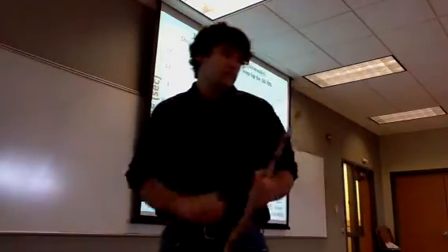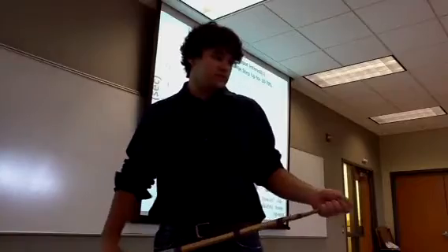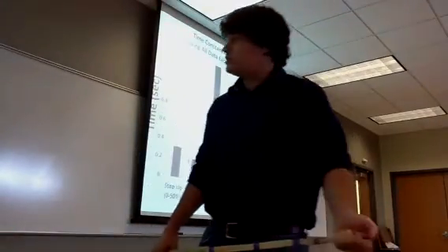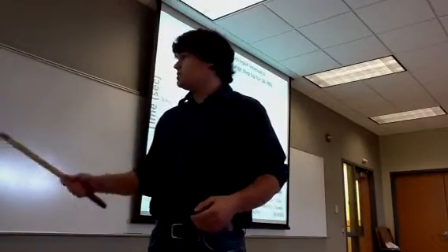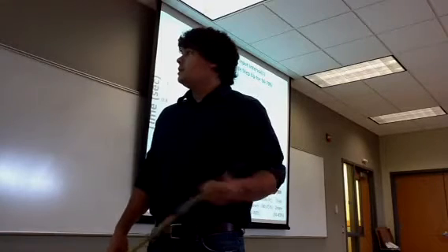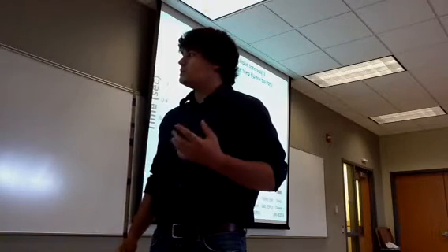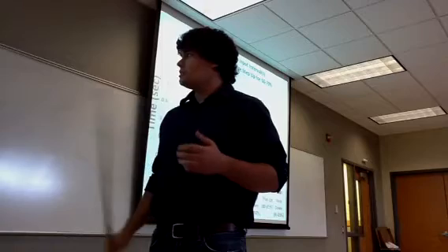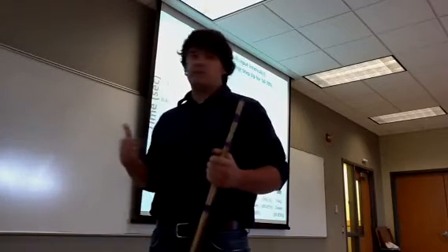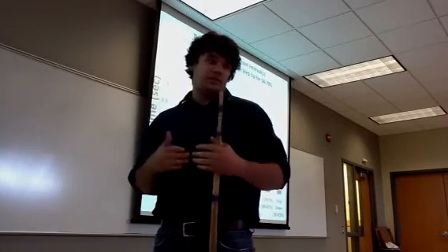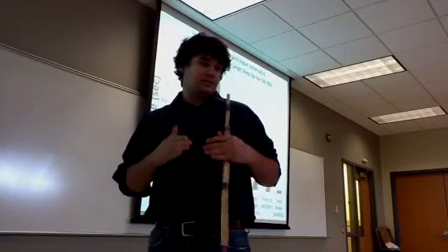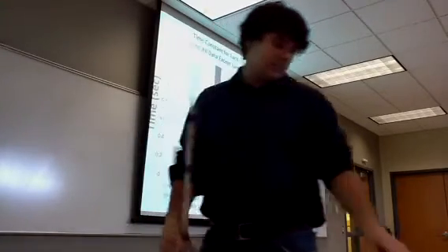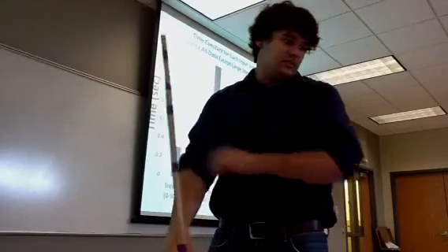From all the step responses that we did on the 4 different sections, they're tallied up in this chart here, step up and step down for the 4 sections. And you can see there isn't a real correlation between any of the sections. You can't really compare them to each other. You just have to analyze each section almost as a separate system, just because of how different it is.